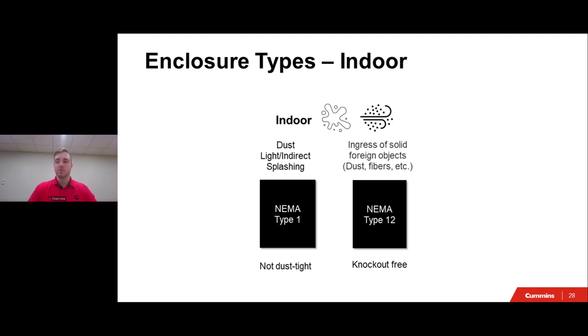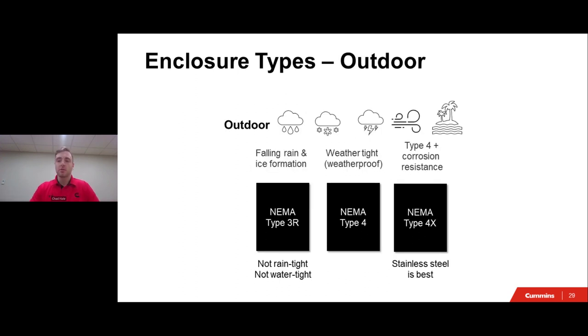So the big differences between the Type 1 and Type 12 being you have those gasketed seals, allowing for a little bit more protection between dust, heavier dirt, as well as light water and oil, but does not protect against pressurized water or oil. So keep that in mind. So those are the indoor enclosures. Now let's talk about outdoor enclosures and what that means for your automatic transfer switch.